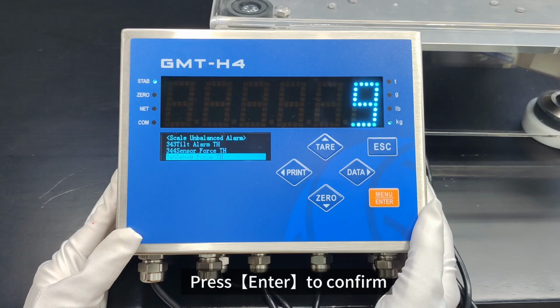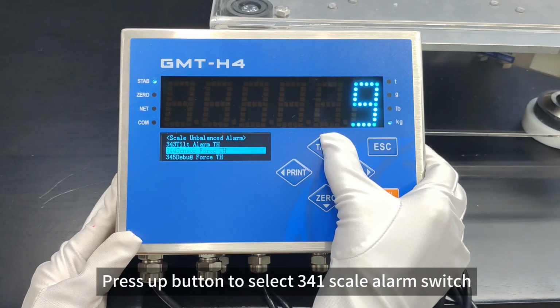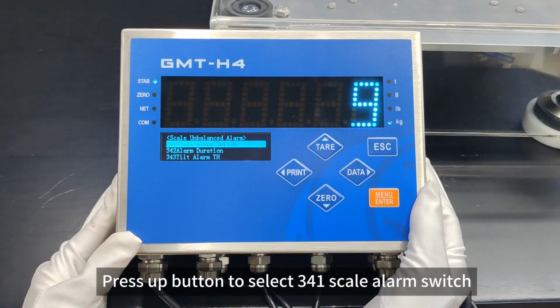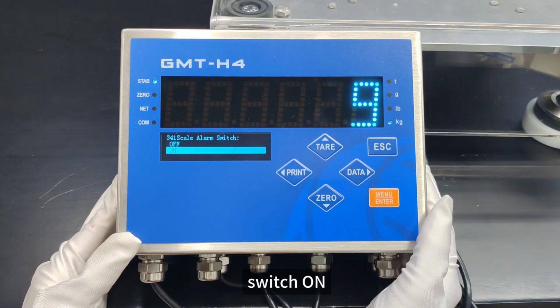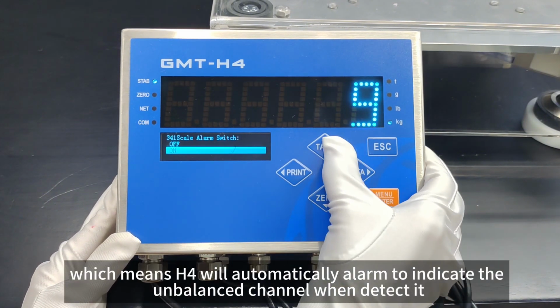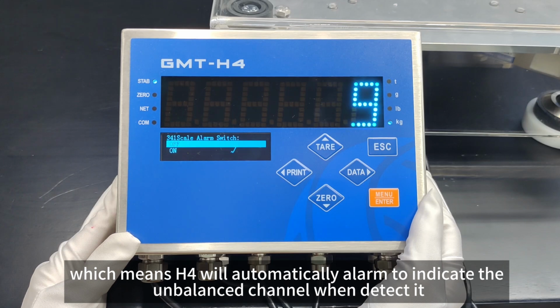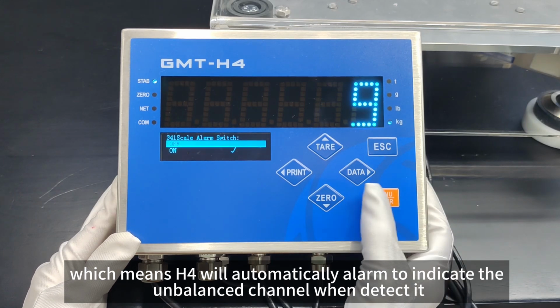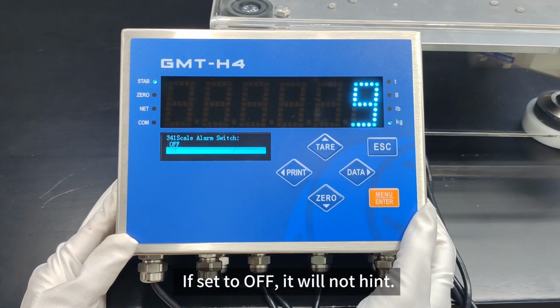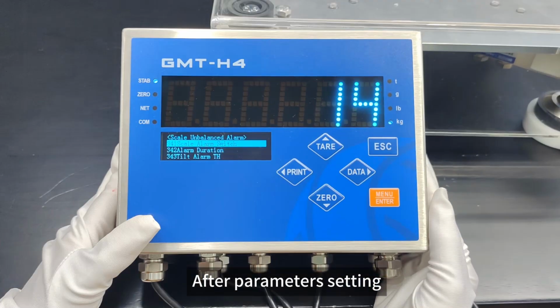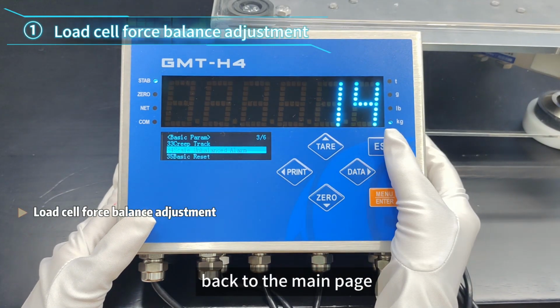Press Enter to confirm. Press the up button to select 341 scale alarm switch. Switch on, which means H4 will automatically alarm to indicate the unbalanced channel when detected. If set to off, it will not hint. After parameter setting, go back to the main page.